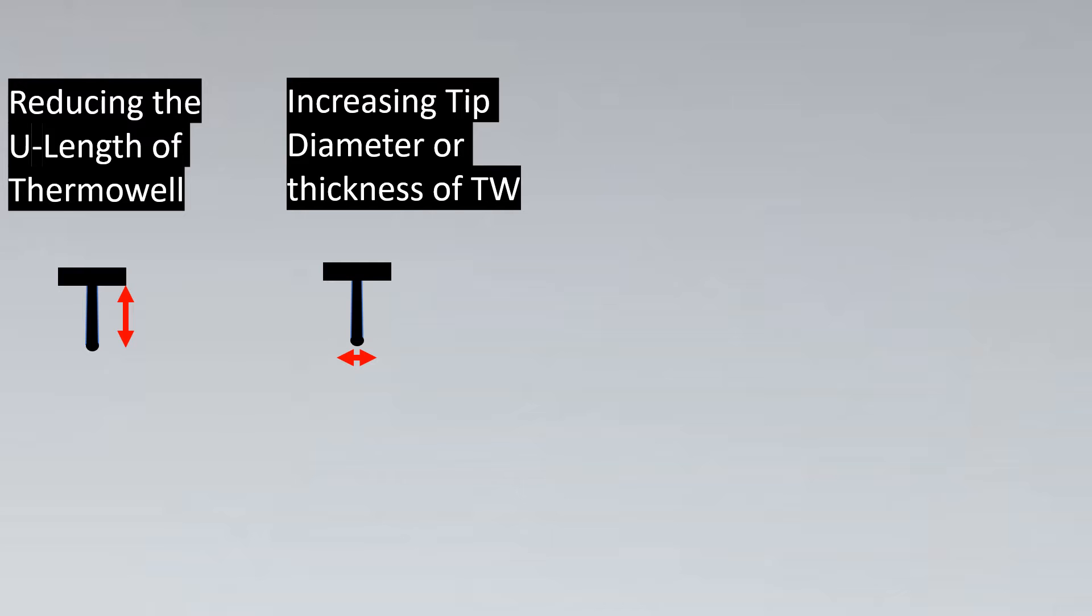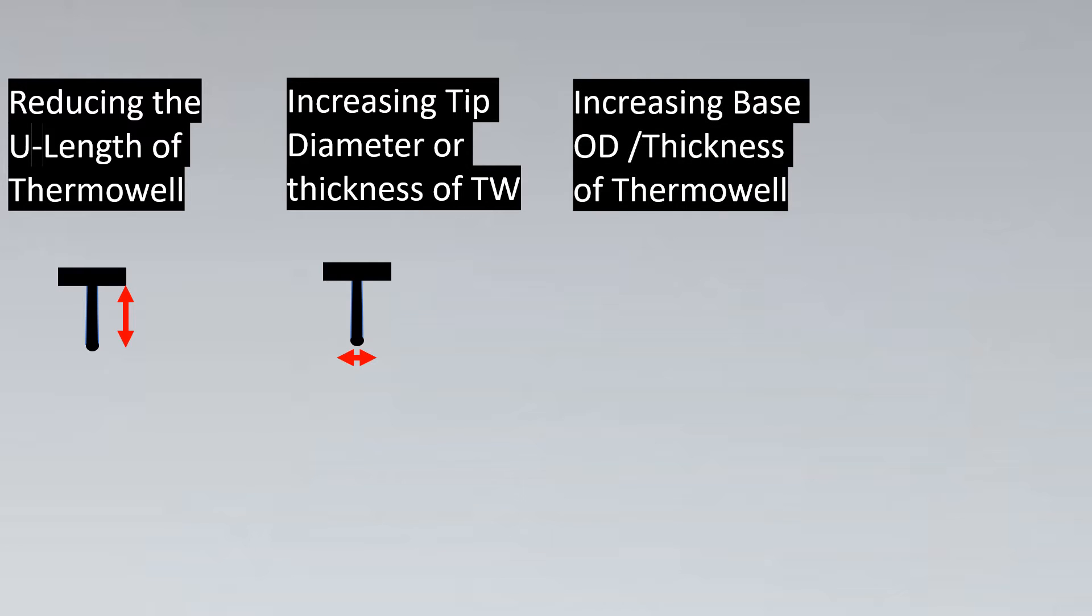If that is acceptable to the client, then we might go ahead with this particular solution. If this solution doesn't work, then we can increase the base thickness of the thermowell. So basically this thickness of the thermowell can be increased, but again there are few important points to be noted.